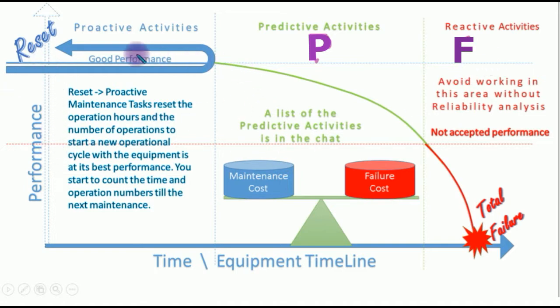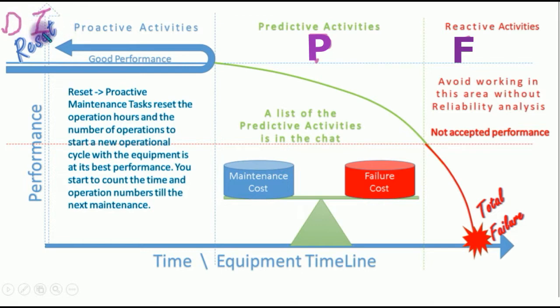This area is the most comfortable part. It starts here — if you had done your design here, and then your installation. Nowadays the curve was extended. It's the D-I-P-F curve — design and installation. You need to consider maintainability during the design and during the installation. During the installation, you take what they call the footprint — the initial records of all the parameters of your machines: performance, current consumption, pressures, flow, timing, and everything you take from your machine. That's your footprint during the installation.